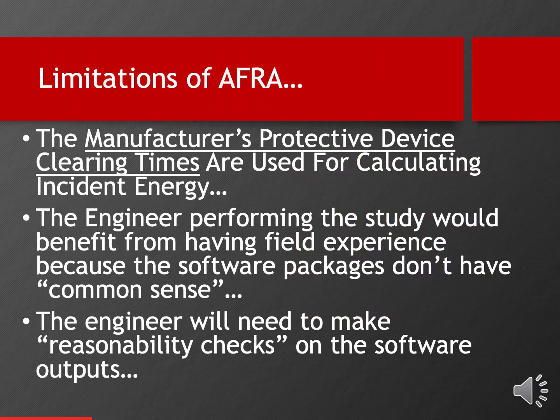Some of the limitations of arc flash risk assessment, and this is extremely important. The first one is the most important point on the whole slide, and that is that the engineering software that we use to do these calculations will use the manufacturer's protective device clearing times for calculating incident energy. That means that the circuit breaker in particular that would be protecting a circuit would operate at the same speed it did when it was brand new.